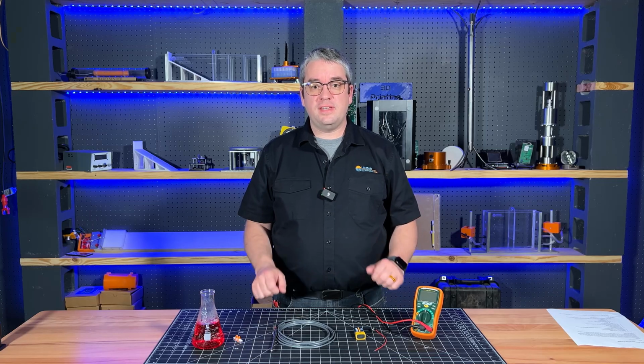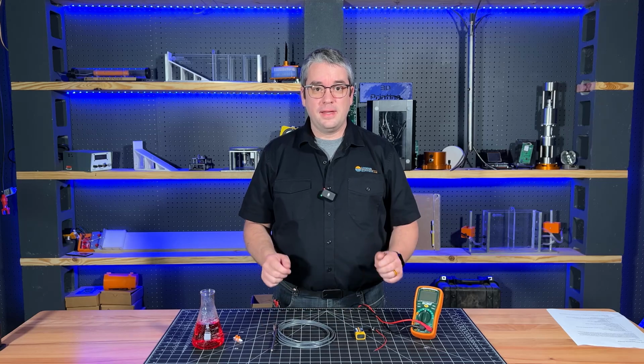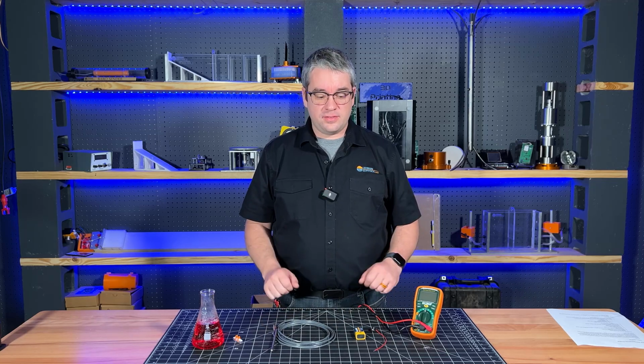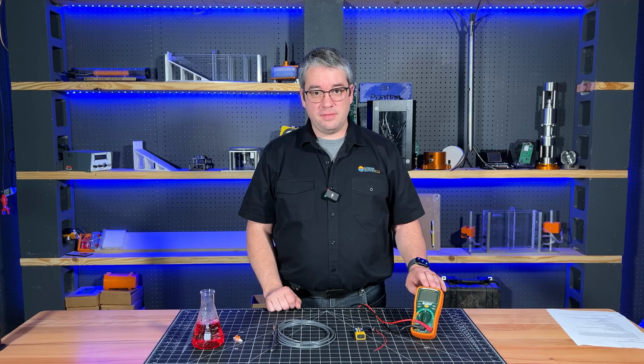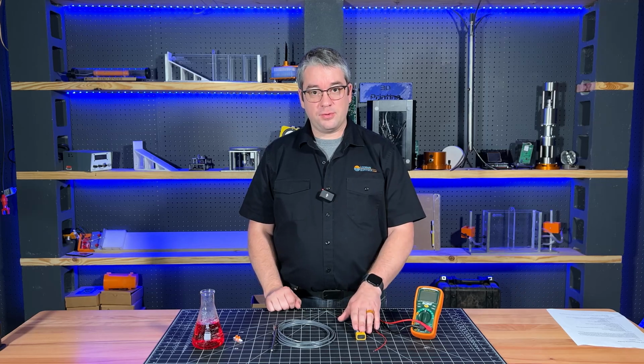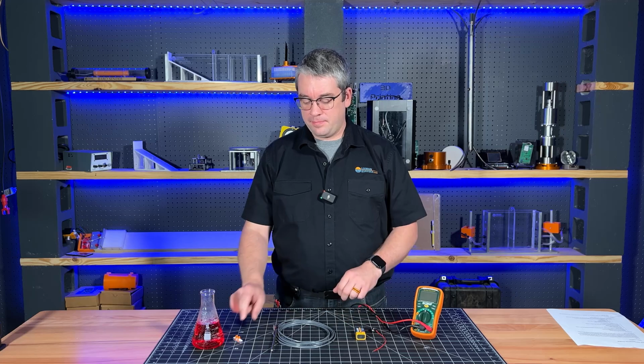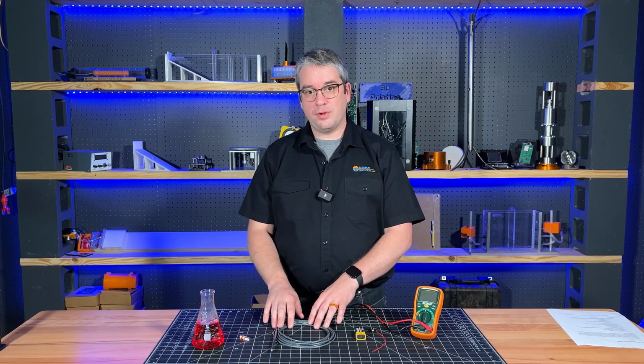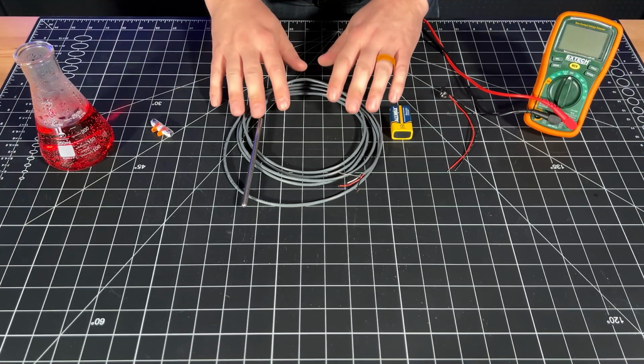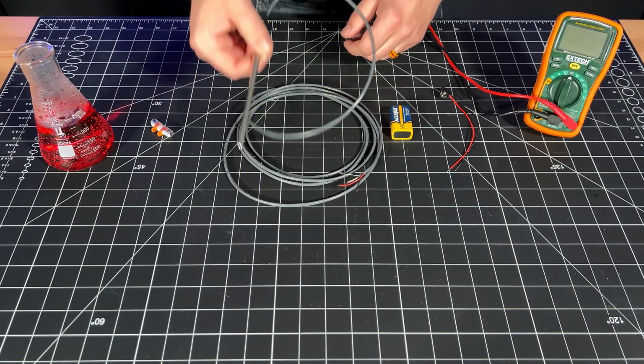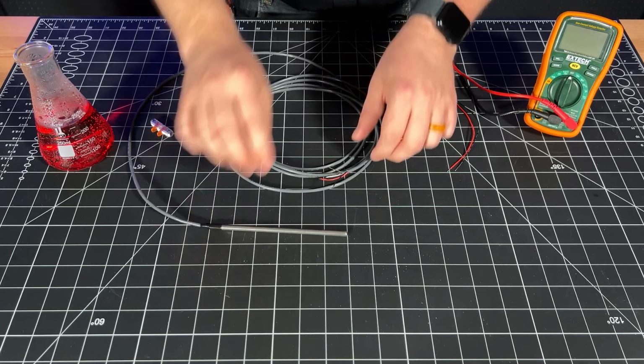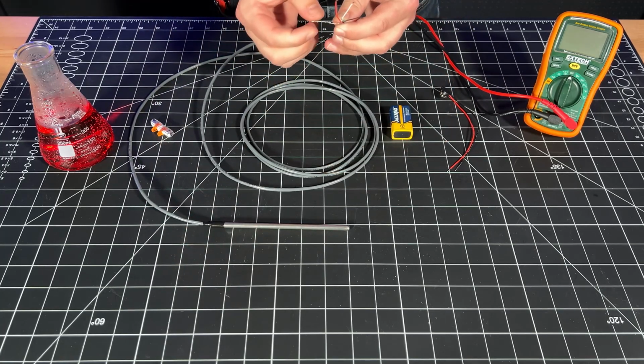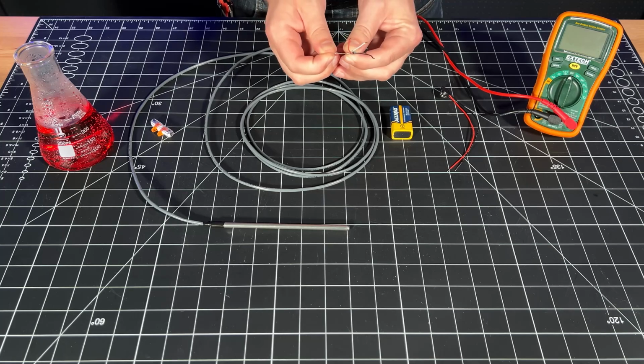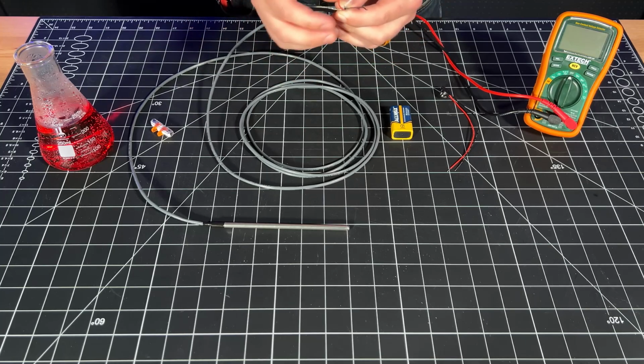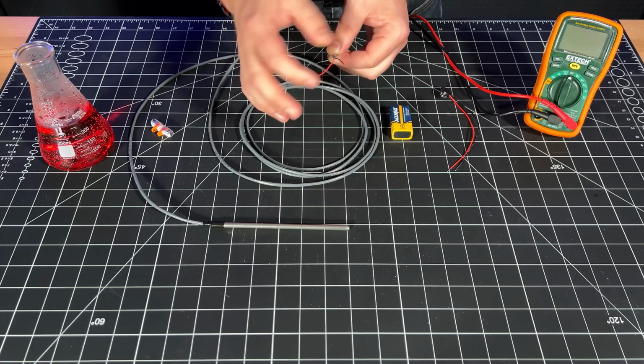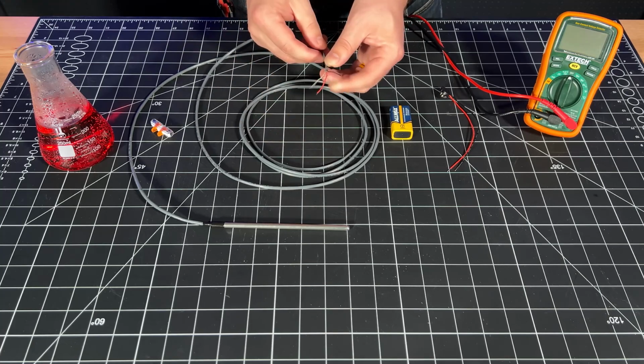So I'm going to show you just how easy it is to hook up the Easy Temperature Probe and take a temperature reading. The only things that I'm going to need are a meter or something to measure the voltage output of the probe, a power source, in this case a 9-volt battery and battery clip, a connector to connect that, my probe, and something to measure. Okay, so to use the Easy Temperature Probe, I'm just going to get a little bit of wire loose here, and you'll notice that there is a shield wire that you can connect to an earth ground if you want to shield the conductors in here from any radio frequency interference. Otherwise, we just have the 3 connections here.